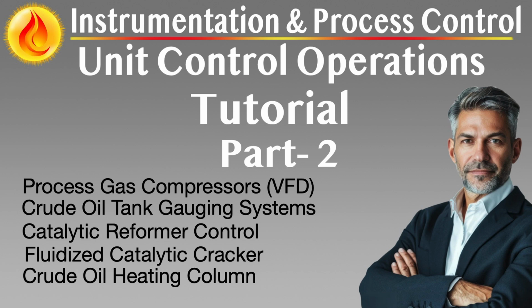Column pressure control is crucial for maintaining the vapor-liquid envelope and ensuring stability in the reflux system. Typically, pressure control valves, PCVs, on the overhead vapor line or vent-to-flare controls are used to maintain column top pressure. In more advanced systems, vapor balancing with downstream gas recovery units or flare header systems is implemented, with APC logic coordinating vent flow to minimize emissions and flaring. High-fidelity pressure control also protects from entrainment of heavier components, which could degrade overhead condensate quality.